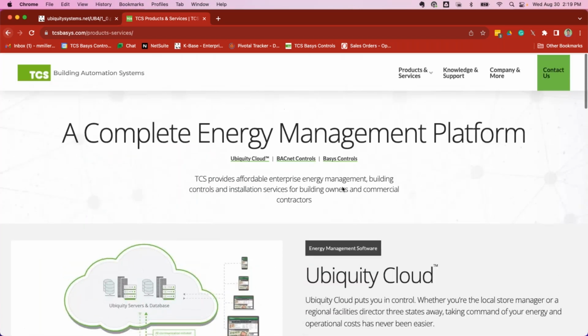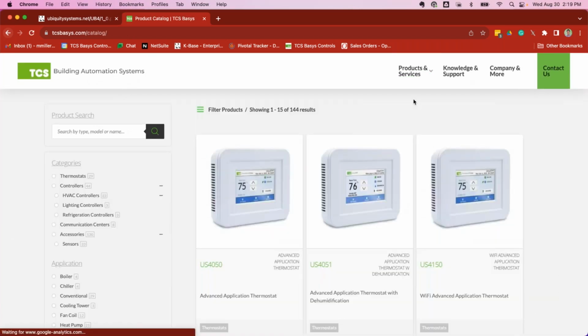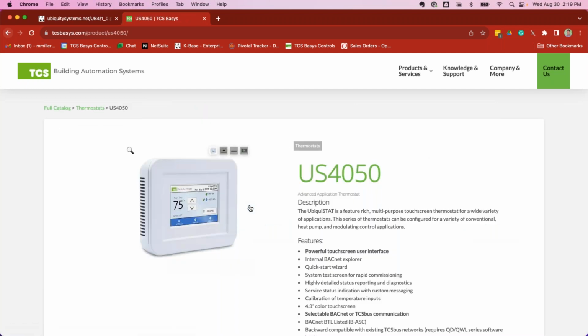I think the other thing I was going to look at doing is going into our Ubiquity a little bit further. So what we essentially do in Ubiquity is we have 4 different sequences of operation. Our full featured version has analog outputs for cooling and heating, but on top of it, an economizer analog out, which gives you the ability to take control of that economizer so that you can maintain the ventilation requirement that's often needed in the space.